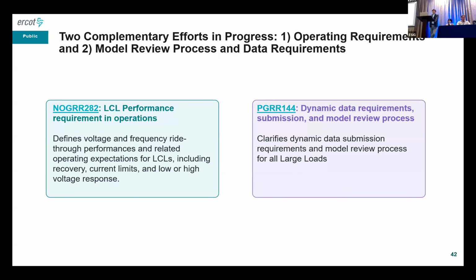So to address all those ride-through issues and load loss issues, we are making two complementary efforts, right, to establish some rules and requirements. So NOGRR 282, Nodal Operating Guide Revision Request 282, has been proposed and submitted. I think it was approved by the board of directors in early June. It's getting close, but it basically defines the voltage and frequency ride-through performance requirements for all large computational load.